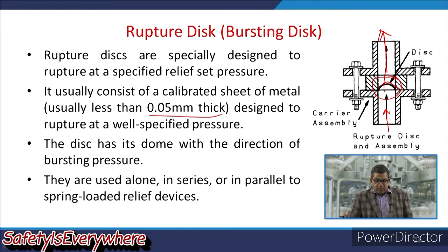Usually this disc has its dome in the direction of the bursting pressure. This one you can see. They are used alone, in series or in parallel to a spring loaded safety valve. Now the ring holding the disc on the vent side is made thicker than the dome in order to protect it later. Here there is a ring. This can be made from a variety of materials, including exotic corrosion resistant material, etc.